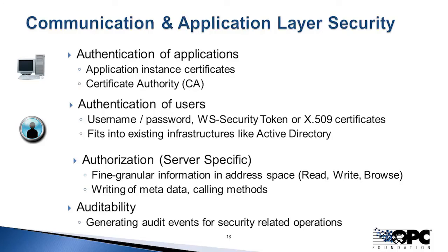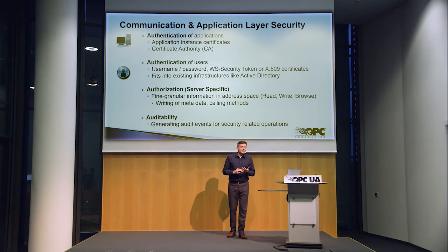Okay, so when we look at that, we've got the authentication of the applications, and we also have authentication of users, and that's where we use either username and password, or we're using certificates. So you're using the tokens or X509 certificates, which is typical. That's what the people from the IT world are very used to. That's a relatively new concept on the OT side, using that in order to build the trust, but that's a well-proven technology, or it's the best of breed that we have right now. Okay, so that's the authentication of users.